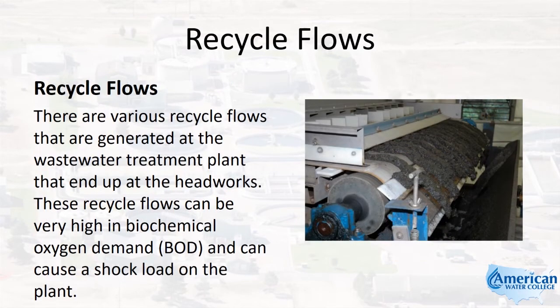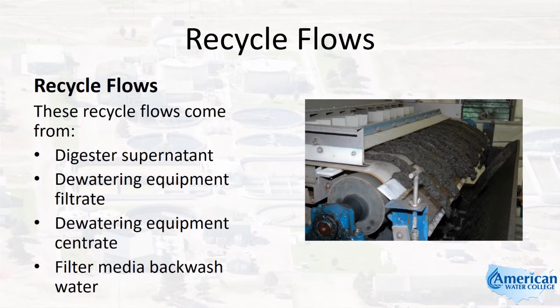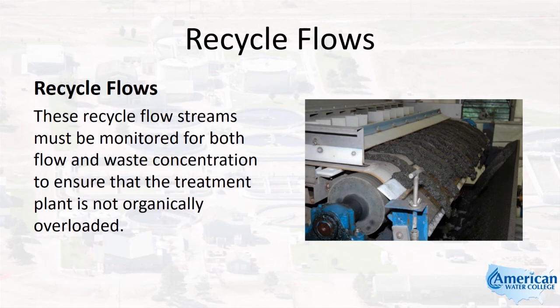There are various recycle flows that are generated at the wastewater treatment plant that end up at the headworks. These recycle flows can be very high in biochemical oxygen demand and can cause a shock load on the plant. These recycle flows come from digester supernatant, dewatering equipment filtrate, dewatering equipment centrate, and filter media backwash water. These recycle flow streams must be monitored for both flow and waste concentration to ensure that the treatment plant is not organically overloaded.